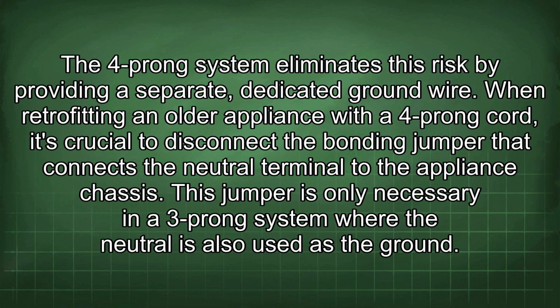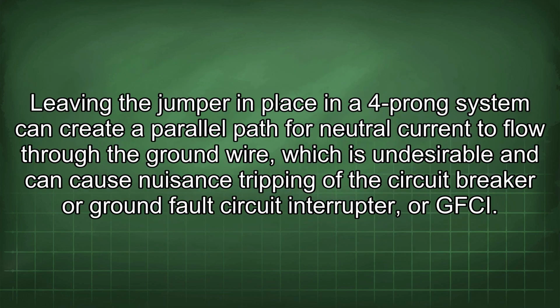The four-prong system eliminates this risk by providing a separate, dedicated ground wire. When retrofitting an older appliance with a four-prong cord, it's crucial to disconnect the bonding jumper that connects the neutral terminal to the appliance chassis. This jumper is only necessary in a three-prong system where the neutral is also used as the ground. Leaving the jumper in place in a four-prong system can create a parallel path for neutral current to flow through the ground wire, which is undesirable and can cause nuisance tripping of the circuit breaker or ground fault circuit interrupter, or GFCI.